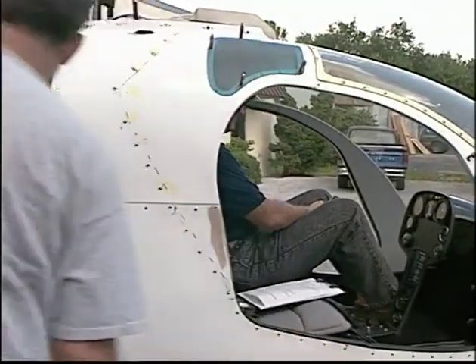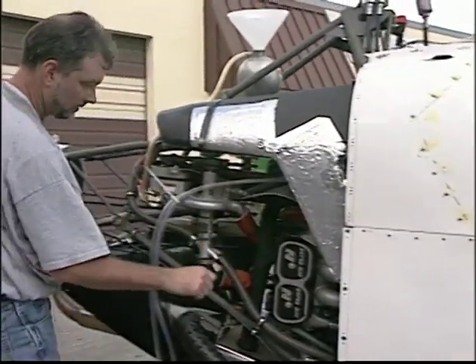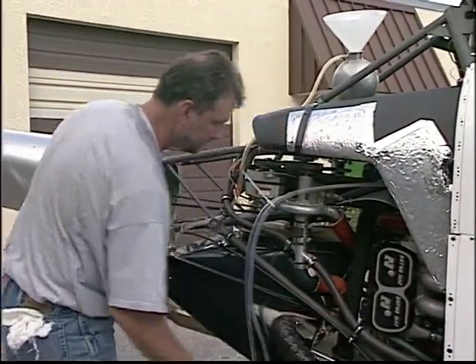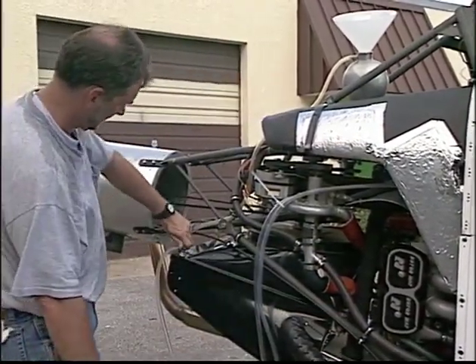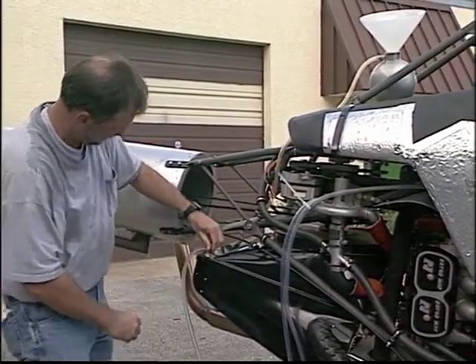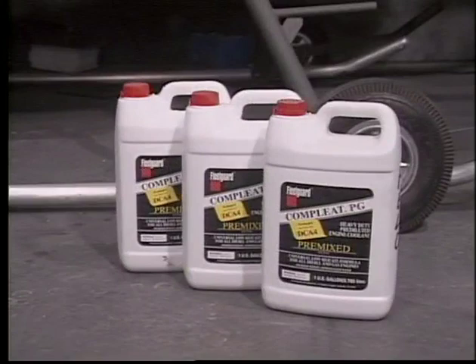The purpose of the idle check is to verify the oil system is operating properly and remove the air from the coolant system without the added dangers of the moving rotors overhead. Propylene glycol is a recommended choice for the coolant antifreeze. Propylene glycol offers improved cavitation corrosion protection and better overall performance than ethylene glycol.